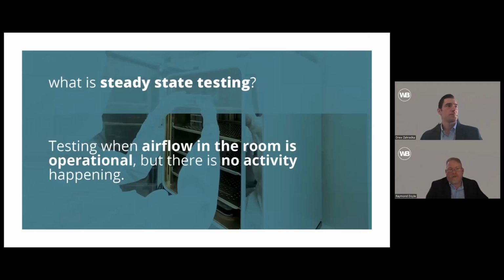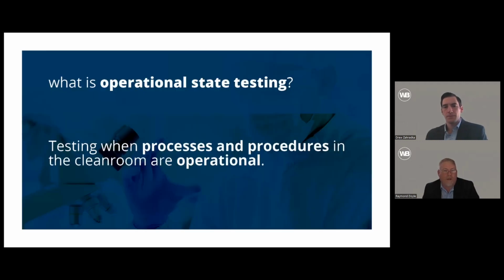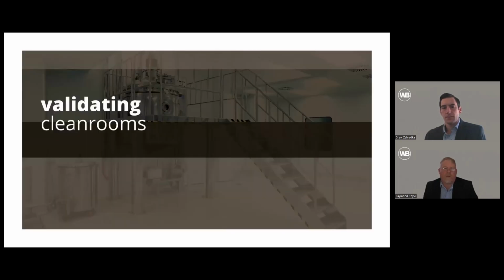Steady state versus operational airflow. This comes into play a lot when we talk about cGMP manufacturing and EU standards. They do require a steady state test without the equipment and people in the room. And it's just the background airflow. And it usually is the easiest test to successfully pass, but then you need to do the operational test that actually takes place when you're doing the process and have people and equipment running. That oftentimes in a very complicated space is nice to have the CFD, so you can have a proof of concept once you have the test done.